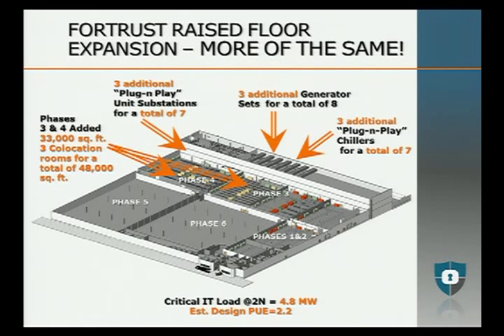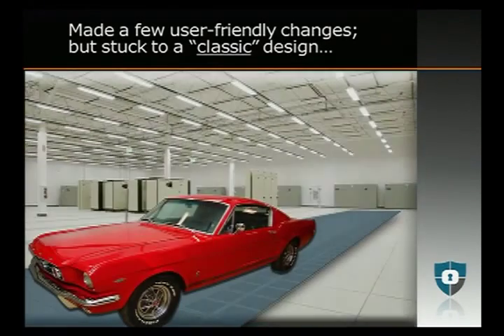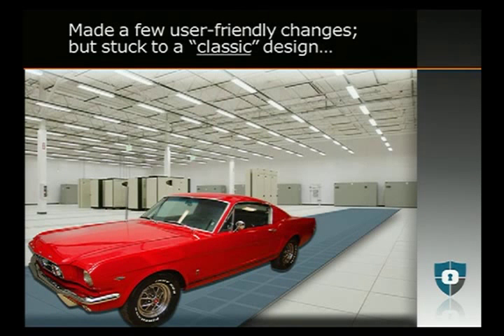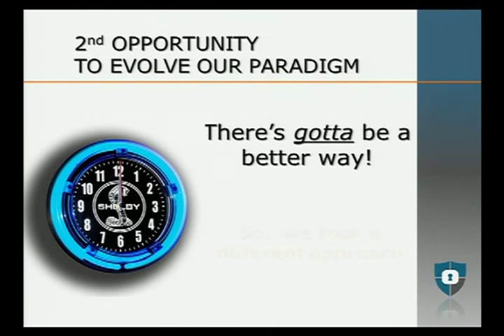So when we went through our first expansion, we actually added 33,000 square feet to the existing facility, phases 3 and 4, as you see there on the screen. We increased the critical IT load to 4.8 megawatts, but our estimated design PUE was still about 2.2. So really what we did was make a few user-friendly changes but stuck to the classical design. We did manage to put a roof on it and some air conditioning in there.